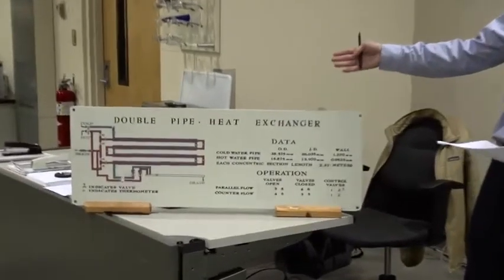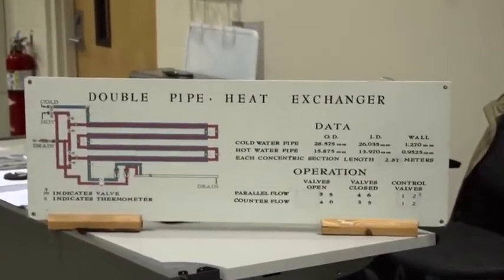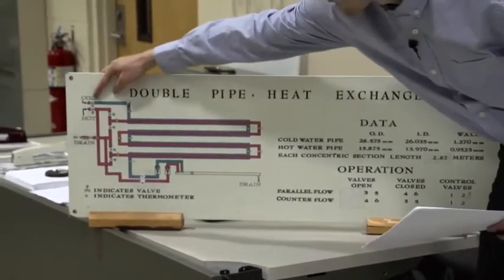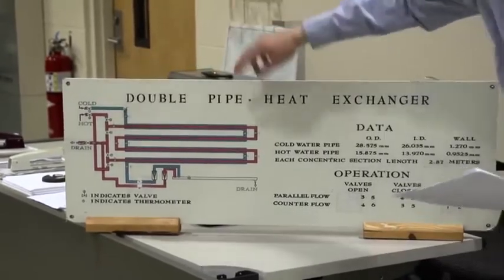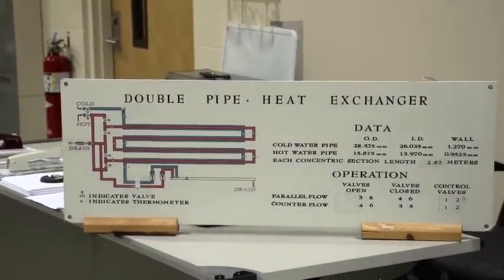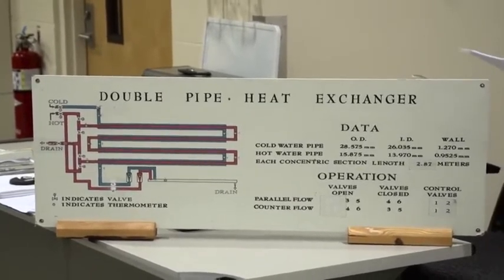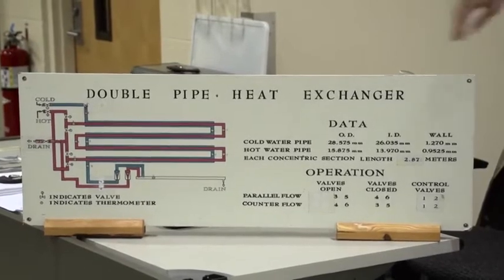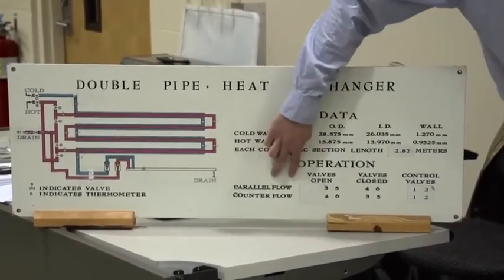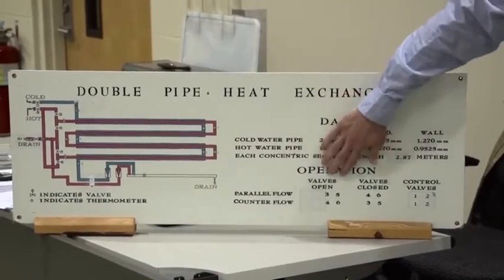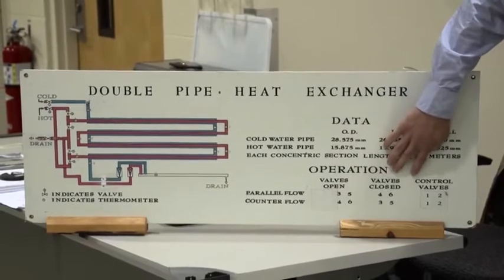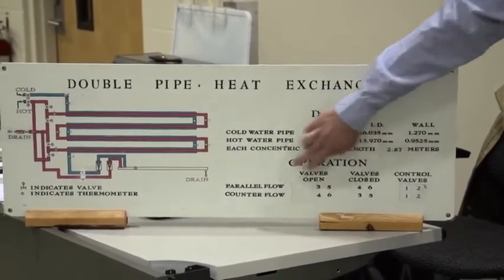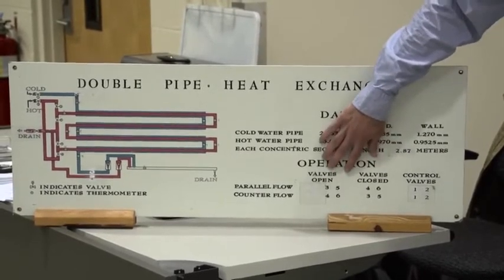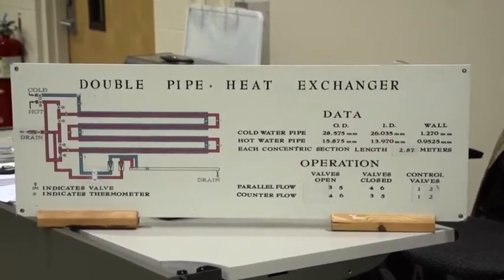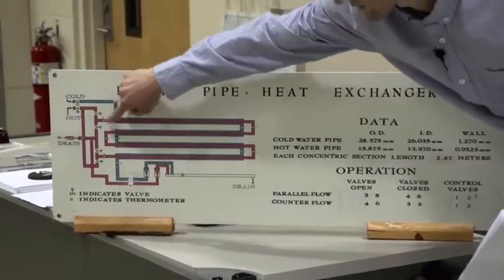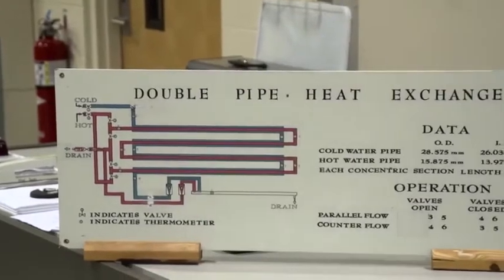Here we have a diagram of this system. You can see there are cold and hot valves, as well as 4 valves for changing the configuration of the heat exchanger, counterflow or parallel flow. And the configuration that you choose is outlined here. For parallel flow, you want to have valves 3 and 5 open and valves 4 and 6 closed. For counterflow, it's just the opposite. You want to have valves 4 and 6 open and 3 and 5 closed. And again, those valves are here. Valves 3, 4, 5, and 6.